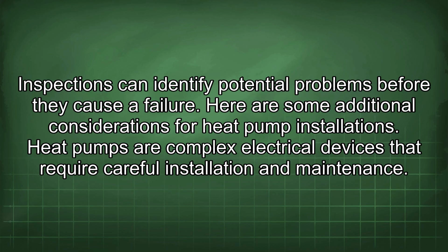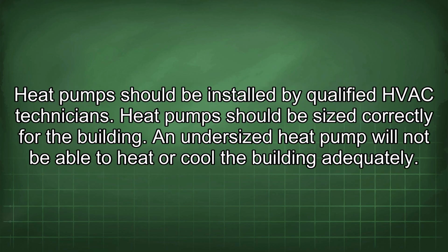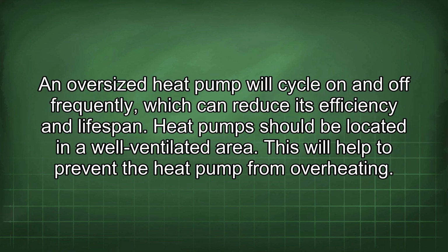Here are some additional considerations for heat pump installations. Heat pumps are complex electrical devices that require careful installation and maintenance. Heat pumps should be installed by qualified HVAC technicians. Heat pumps should be sized correctly for the building. An undersized heat pump will not be able to heat or cool the building adequately. An oversized heat pump will cycle on and off frequently, which can reduce its efficiency and lifespan.